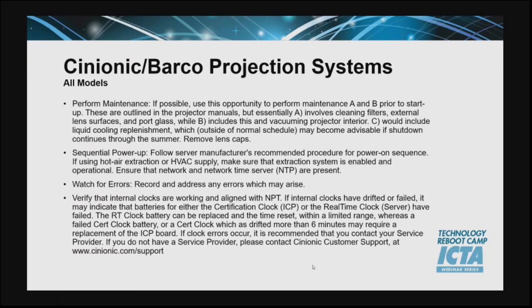One thing to make sure of, throughout doing the sequential power-ups every 7 days or every 3 days, is that your real-time clock and ICP clocks, along with the NTP time server, are syncing up properly. In some cases, if the time drift gets more than 6 minutes, you might be required to replace an ICP board. If you notice any errors like that, please reach out to your NOC service provider or the individual manufacturer.